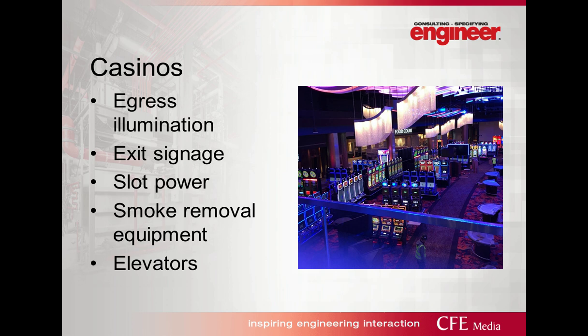So while 1 foot candle average is a minimum requirement, it doesn't mean it has to be the minimum you apply. You may decide to put 10 foot candles. You have to think about the people that are using these machines also. A lot of them are elderly and don't have good eyesight. It's harder for them to get around. So take that into consideration.